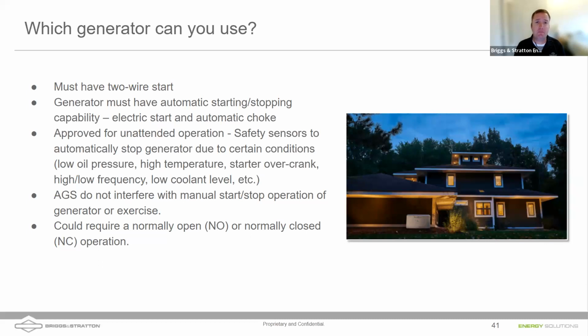Really, one thing to keep in mind, though, is that a lot of times I like to leave our controller programmed to do the exercise cycle. A lot of our generators are programmed to come on once a week and run for a little bit of time to start up and test themselves. You could theoretically have the inverter doing that functionality, but a lot of times I leave that to the generator to do its thing, or its biannual 45-minute burn off as well.